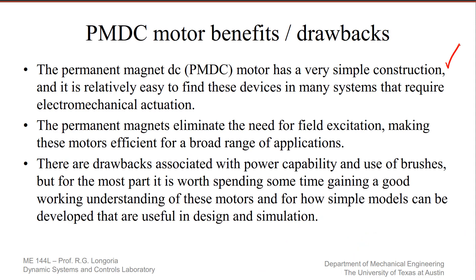Some benefits again were listed on that table: simple construction, you find these in many devices, and you don't need external power to run them — you get permanent magnets to give you the field excitation. You'll see them used in a broad range of applications. Some drawbacks are that they do have lower power capability and the brushes sometimes aren't desirable — they do wear, and for some applications like in clean rooms, these would shed particles, so you wouldn't want brushed motors there.